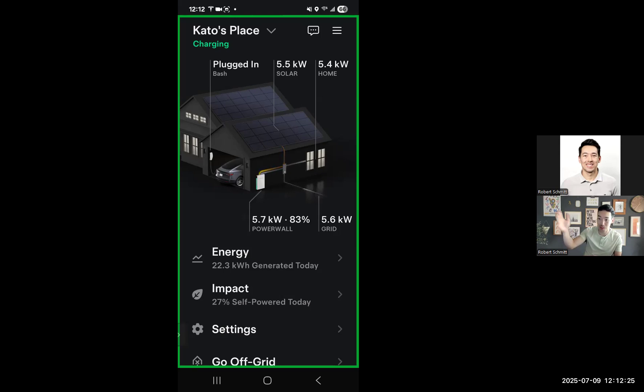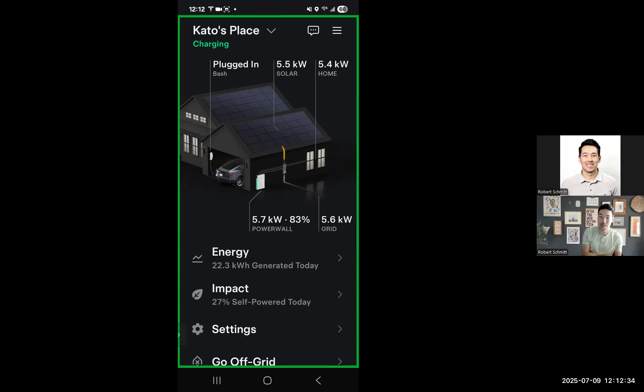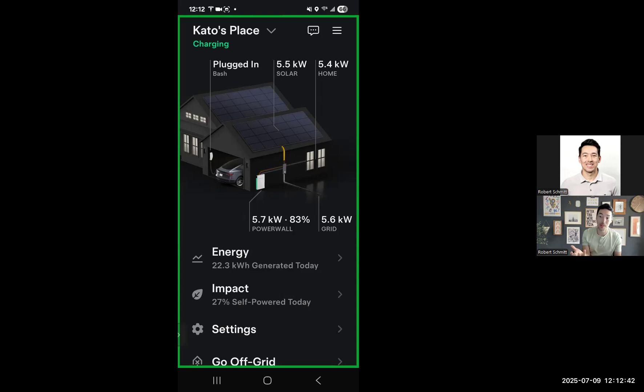The biggest risk here is if you have an outage, there's a storm, you have an outage at two in the morning, your Powerwall is not charged when it should have been. It should have been at 100%. That's the point, there's a safety aspect of this, and there's no user-facing setting to revert the firmware update. And so that is the permanent fix, reverting the firmware update.